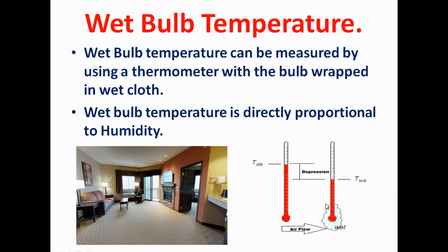When our surrounding air has 100% relative humidity, there will be no evaporation of water from the wet cloth, and when there is no evaporation, there will be no cooling effect on the bulb of this thermometer. So in such condition, the wet bulb temperature will become equal to the dry bulb temperature and this depression will become zero.